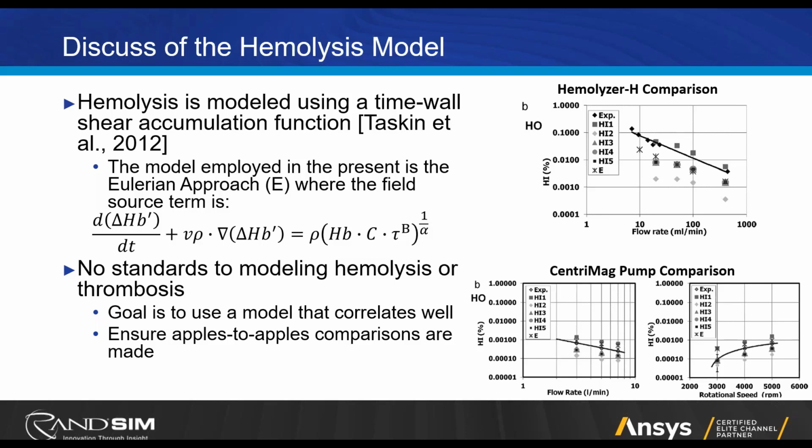And so again, it's using all of this data together, combined with the experimental data, to really accentuate what your designs can do, where their strong suits and weaknesses are, and where you're potentially going to see issues as you move down the road into clinical trials or fabrication of the final device itself, and how it might perform at the end goal. Whenever we do these, we're always making sure we're doing apples to apples comparisons. We use the same hemolysis model across our prototypes to give a broad stroke picture of what is going to happen. Which design do I have that's going to operate the best?